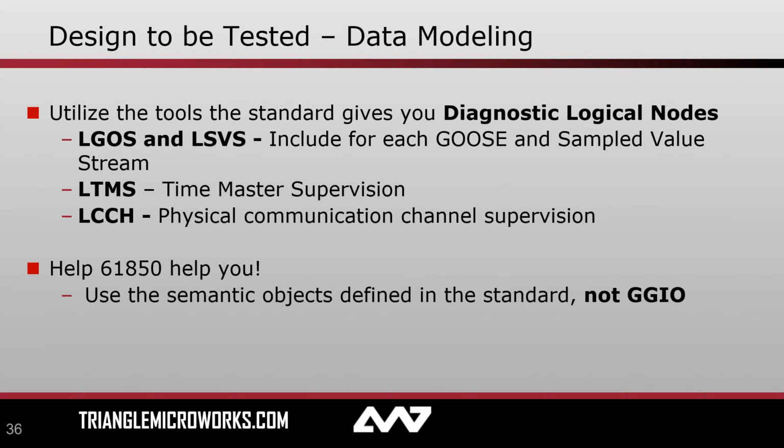Next, a little bit about data modeling. This falls into two parts, but it both revolves around the idea that you need to take advantage of the tools that the standard gives you. So LGOS and LSVS exist. Most major manufacturers support them at this point. It might be up to you as someone who's configuring this SCD file to actually utilize them if it's not done automatically by your system configuration tools. So please take advantage of them.